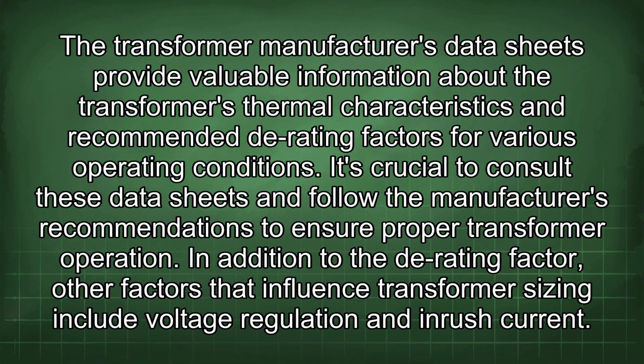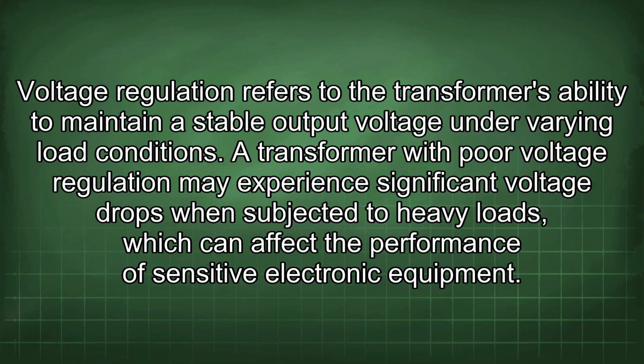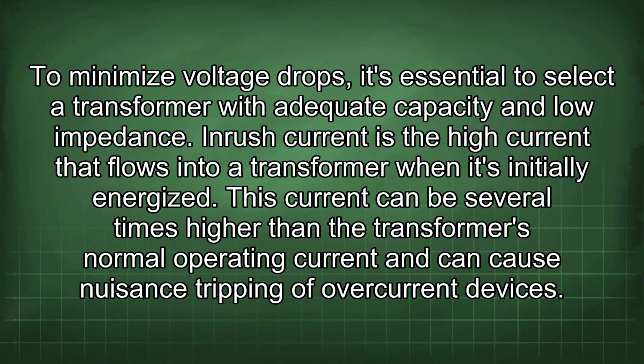The transformer manufacturer's datasheets provide valuable information about the transformer's thermal characteristics and recommended derating factors for various operating conditions. It's crucial to consult these datasheets and follow the manufacturer's recommendations to ensure proper transformer operation. In addition to the derating factor, other factors that influence transformer sizing include voltage regulation and inrush current. Voltage regulation refers to the transformer's ability to maintain a stable output voltage under varying load conditions. A transformer with poor voltage regulation may experience significant voltage drops when subjected to heavy loads, which can affect the performance of sensitive electronic equipment. To minimize voltage drops, it's essential to select a transformer with adequate capacity and low impedance.